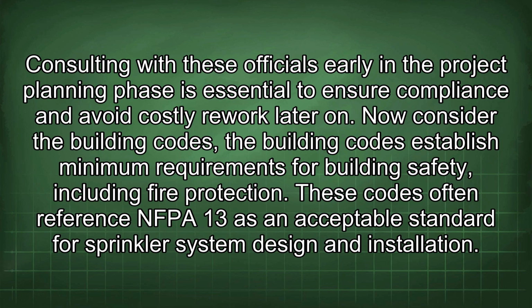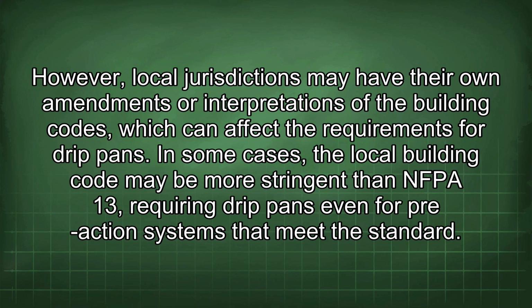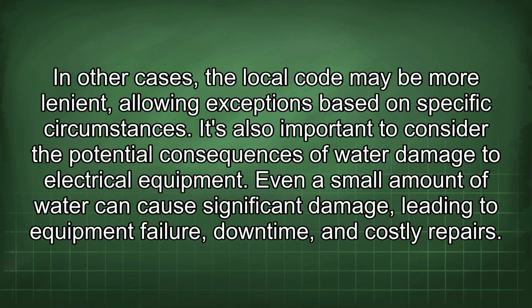Now consider the building codes. The building codes establish minimum requirements for building safety, including fire protection. These codes often reference NFPA 13 as an acceptable standard for sprinkler system design and installation. However, local jurisdictions may have their own amendments or interpretations of the building codes which can affect the requirements for drip pans. In some cases, a local building code may be more stringent than NFPA 13, requiring drip pans even for pre-action systems that meet the standard. In other cases, the local code may be more lenient, allowing exceptions based on specific circumstances.